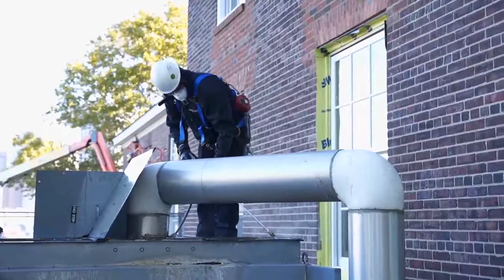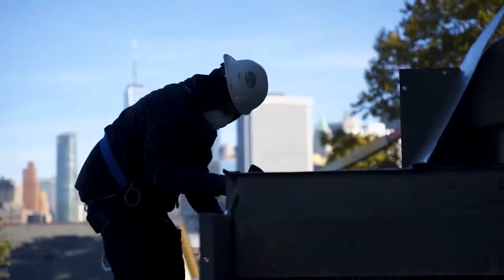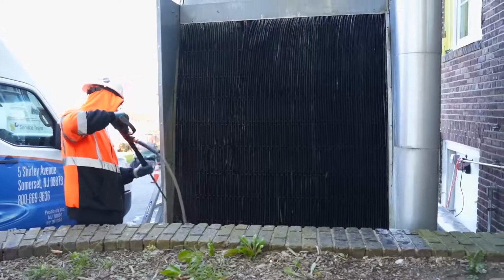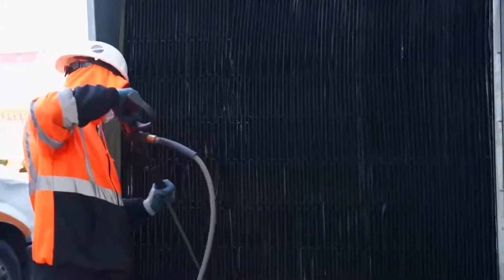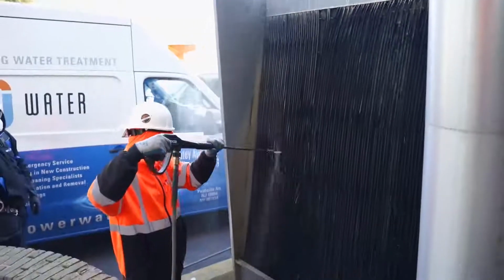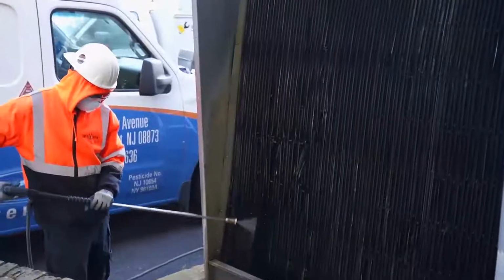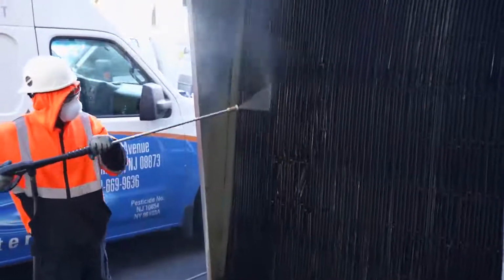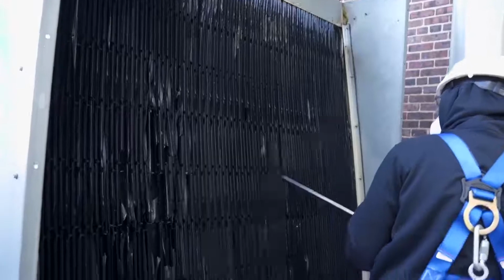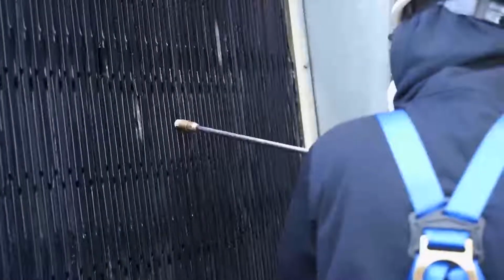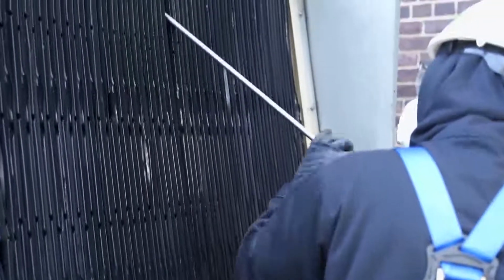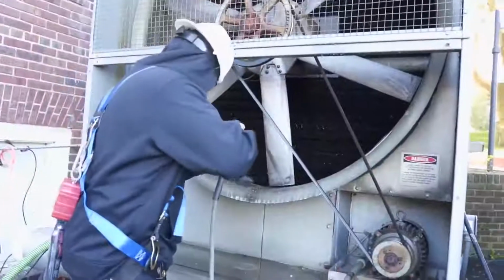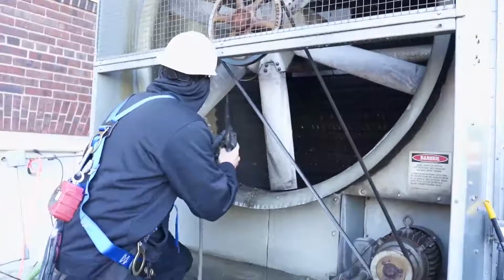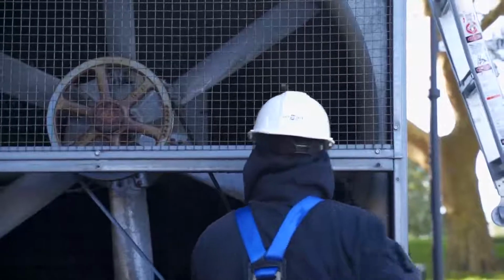Begin cleaning the tower system from the top down, then outside to inside without damaging the plastic parts or stripping coating off metal surfaces. Try to clean every surface as long as it doesn't put you in danger. Include cleaning the cement and stanchions that hold the tower off the ground. If areas around the tower have algae on them, clean them off as well. Notice the tech spraying through the fans? This is why electrical lockout is required.